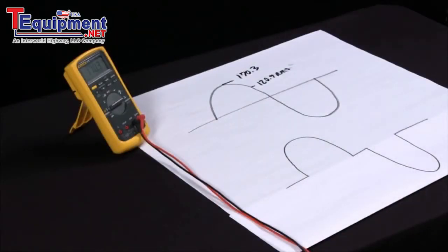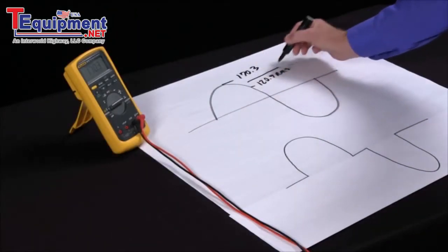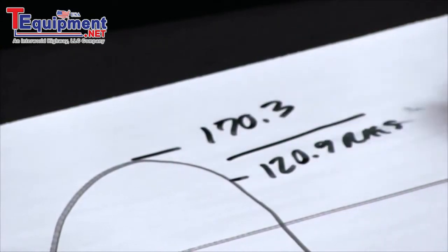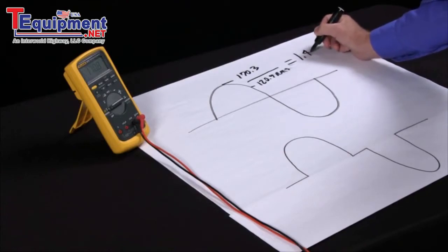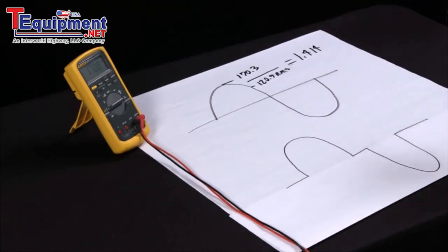Now there's something called the crest factor, which if I divide the RMS into the peak on a nice clean sine wave, this should come to 1.414. Now we can all divide 120.9 into 170.3 and come up with 1.414.